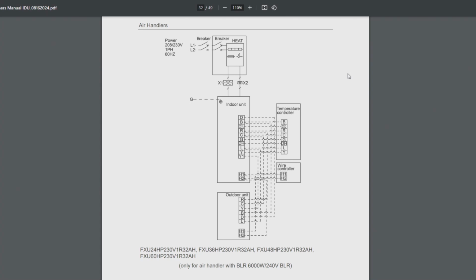So whether the heat pump was running, electric heat, or both, it's going to cease operation of electric heat. It's going to cease operation of the compressor outside, turn the blower on high speed, and it'll remain that way until the sensor clears. Once the sensor clears, it will allow the heat pump to start back up, or it will allow the electric heat to come back on.